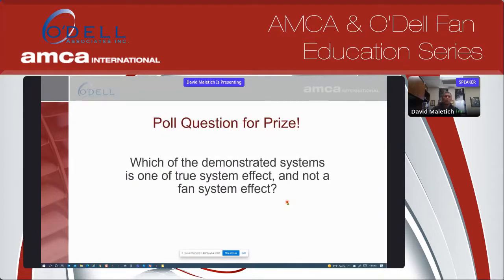So this opens up to what our poll question is. All the system effects that are shown in the demo directly affect or change how a fan performs. And what we mean by that is each one of them is going to change the shape of the fan curve. However, there's one system effect that doesn't affect the fan curve, but does change the system curve. So anyone who can pick that one out will win a prize, and we'll talk about that at the end.